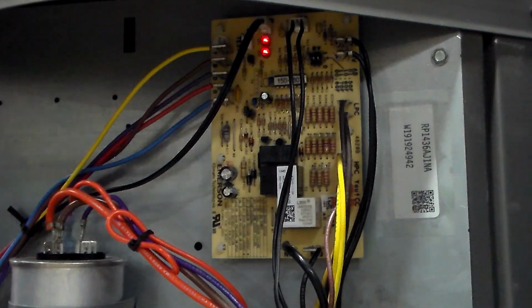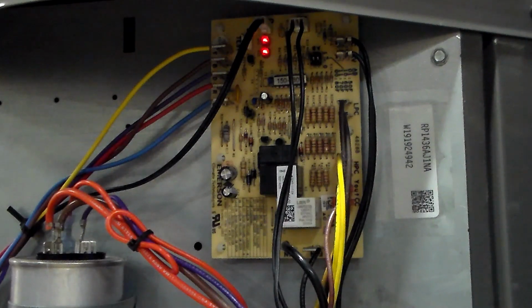Okay, now lastly we have a Rheem. Now Rheem and Ruud are basically the same, but they do everything backwards of everyone else. Most manufacturers are going to fail into heat mode, which means their reversing valve is not energized in heat mode. It's only energized in cool mode. Rheem does it the opposite, and I don't want to get into the logistics as to why they do that, other than just to say that I agree with their philosophy. But they're the only one that does that. Everyone else has fail into heat mode. Rheem is fail into cool mode.